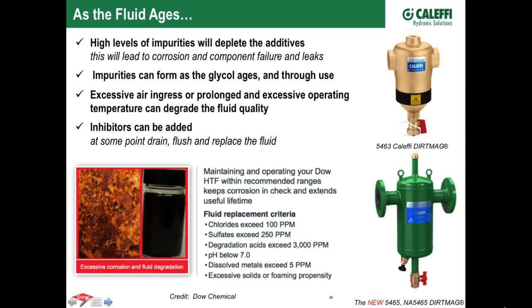This gives a pretty good example of criteria if you're going to blend your own glycol - buy straight glycol and blend it on the job site. This comes from one of the Dow spec sheets for what the water you're using needs to meet. They talk about parts per million on chlorides, which you can read with your TDS meter. They break it down into different minerals, sulfates and chlorides, but a TDS meter reading below 100 parts per million on your water is adequate for blending.